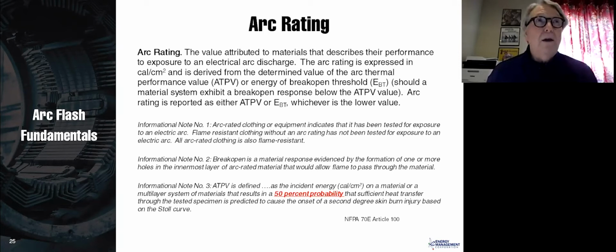So I've been telling you all along, if you have 12 calorie gear and you're working on a 12 calorie system, you're not going to get a second degree burn. By the way, I made this in red. It's not in red in the standard, but to me, this is like, what? It doesn't say you will be protected. It says there's a 50% probability you will be protected. Well, what the heck is going on there? Well, it is what it is. But I would say that's the bad news.